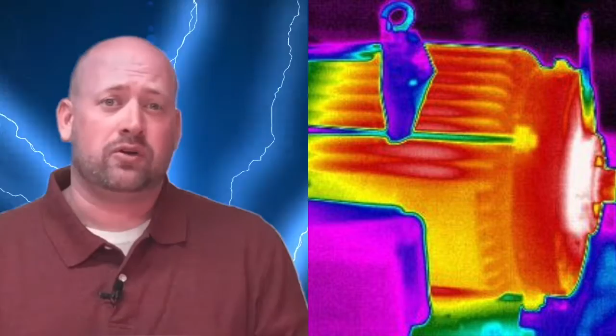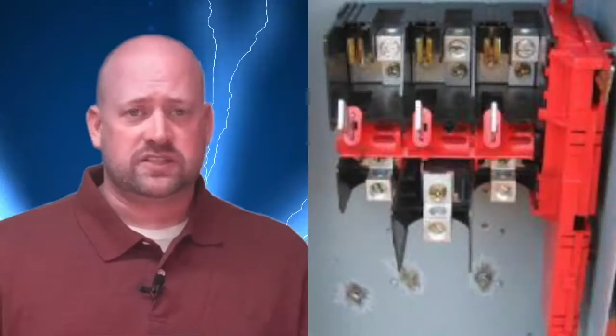So what happens when a transient gets into a power system? Now, electronic devices may operate erratically or at decreased efficiencies. Motors will run at higher temperatures and normal timing can be interrupted, producing vibration and noise. And lighting systems will fail early as well. One of the most common indicators of transient activity is the premature appearance of black rings at the end of fluorescent tubes. Now, transients also affect the contacting surfaces of switches, disconnects, and can cause nuisance tripping of circuit breakers. Transformers are also forced to operate inefficiently and can run hotter than normal as well.